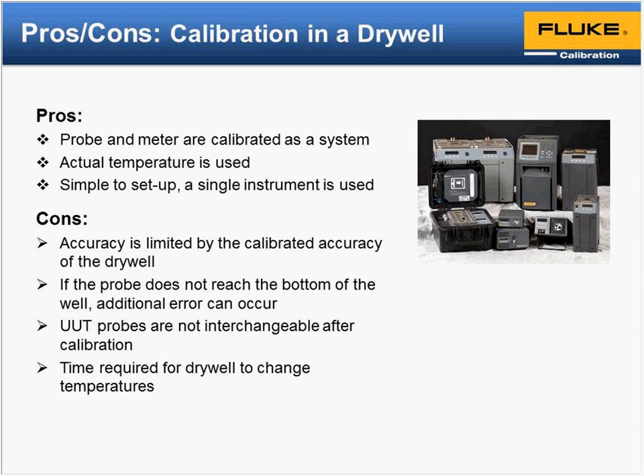Calibrated as a system. We're using temperature, and again, it's really simple to set up. You're just matching your probe to an insert size, and then you're off and running. Some of the cons that you may run into doing the method, again, it's all about balancing what is required by your thermometer readout versus what's available in the different units. Different dry wells do have varying accuracy limits.